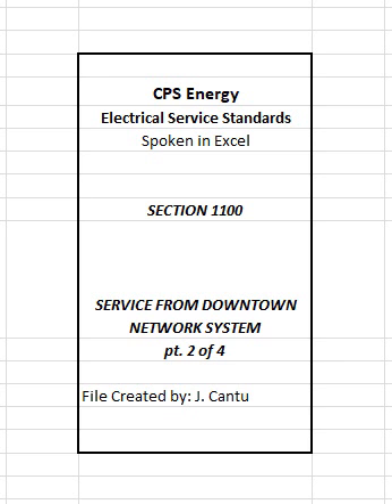Where space is not available on or immediately adjacent to customer's premises, then customer shall construct a transformer room within their premises. Construction of transformer room shall be coordinated, inspected, and approved by CPS Energy's Network Engineering Section. CPS Energy will not construct transformer vaults or rooms on or within customers' premises.